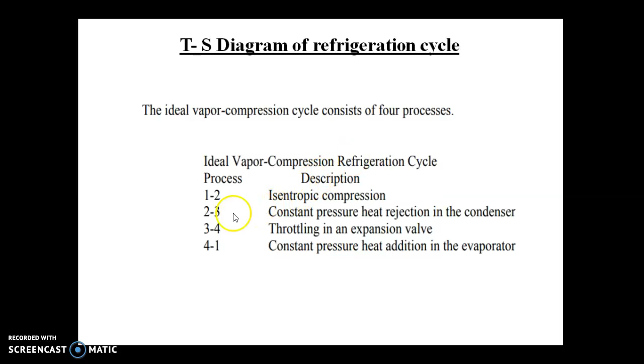The process 2 to 3 is constant pressure heat rejection in the condenser. In the T-S diagram, this is the constant pressure curve. The condenser is a heat exchanger, a phase change heat exchanger. It cools the refrigerant from the superheated state to the saturation state and changes the phase of the refrigerant from vapor to liquid. In the T-S diagram, this is the saturated liquid line and this is the saturated vapor line. This is the superheated zone. The temperature of the refrigerant decreases from superheated temperature to saturation temperature. At the same temperature, the refrigerant changes from vapor phase to liquid phase.